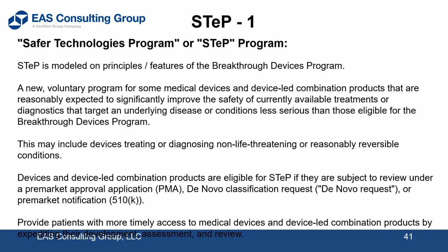Now, as I mentioned before, that doesn't change the method of submitting a request for marketing. It still would be a 510(k) or a de novo or a PMA. All it does is expedite the review process of that submission, because the FDA is involved early on, before you submit, as to what you're doing and what the issues are, and they're aware of it.